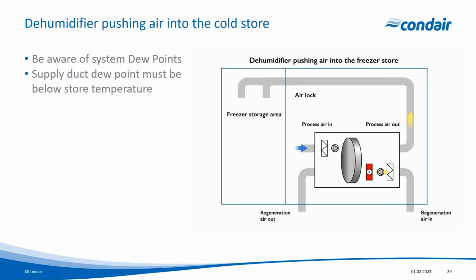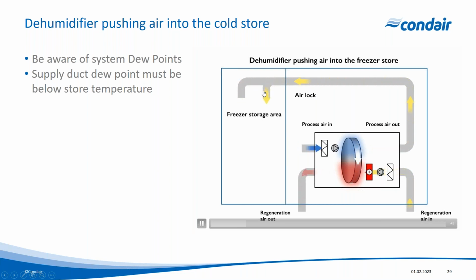You can take air from the chill store and run it through a dehumidifier and feed that air into the freezer area. But beware, because we're going to have different dew points, and we could have condensation forming in our ductwork. So it is one to be a little bit cautious of. So again, supplied duct dew points must be below the store temperature, otherwise we run the risk of ice forming. But we do have the other benefits of having it in the chill store. So 30mm insulation, and you can have a PLC option, and it's easy to access. And again, you can turn the unit off.